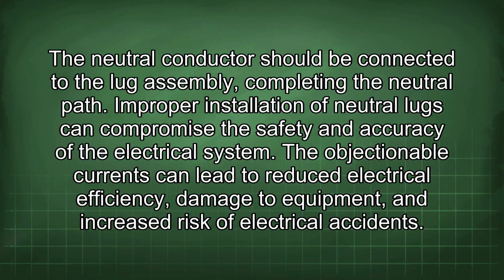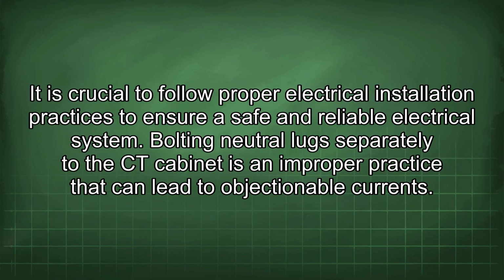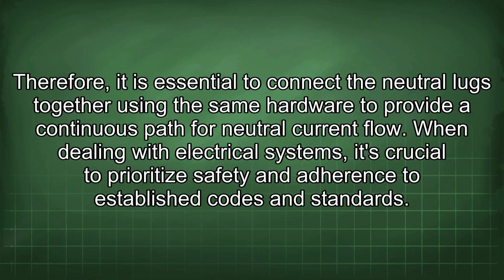The objectionable currents can lead to reduced electrical efficiency, damage to equipment, and increased risk of electrical accidents. It is crucial to follow proper electrical installation practices to ensure a safe and reliable electrical system. Bolting neutral lugs separately to the CT cabinet is an improper practice that can lead to objectionable currents. Therefore, it is essential to connect the neutral lugs together using the same hardware to provide a continuous path for neutral current flow.